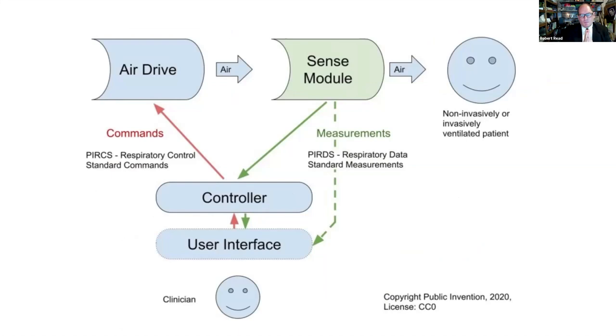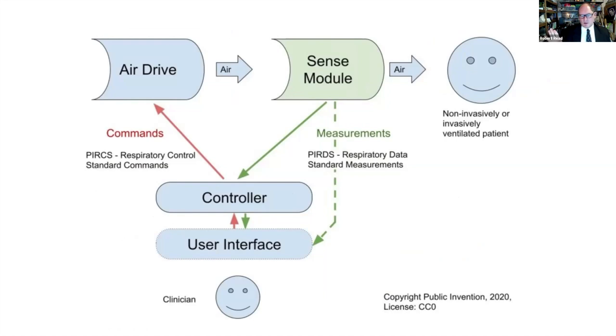This is a model of every ventilator. Every ventilator has an air drive which goes into a sense module of some kind and then goes to a patient. When I say ventilator, I mean primarily non-invasive ventilation. It's been pointed out previously by Florin that invasive ventilation is a very difficult technology to deploy, but non-invasive spontaneous breath support is easier to deploy.